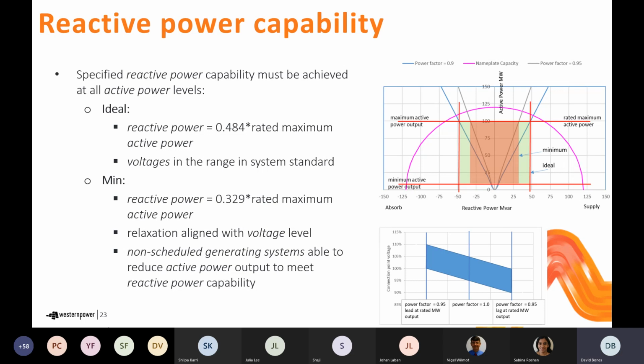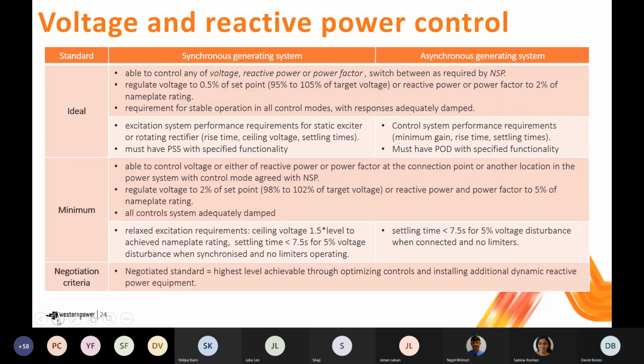So in general, the range covered here by the ideal and minimum standards represents the range that's typically been considered by exemption requests that have come into Western Power. So we think that having this negotiated range available should reduce the need for exemptions in the future, because it should be possible to negotiate an appropriate generator performance standard. And again, each of the requirements we've expressed, and will continue to express today, are equivalent to those defined in the current version of the WEM rules.